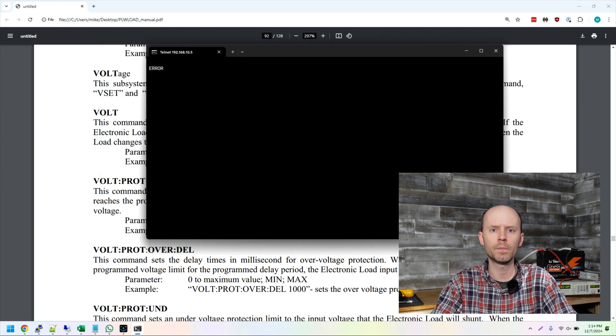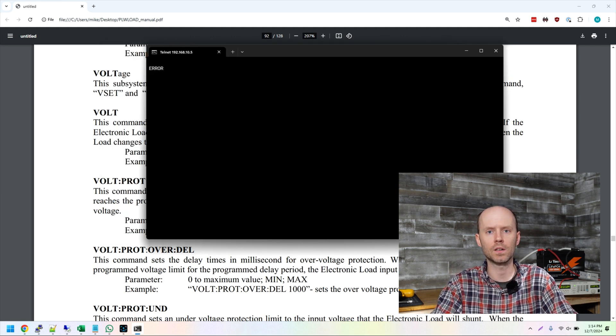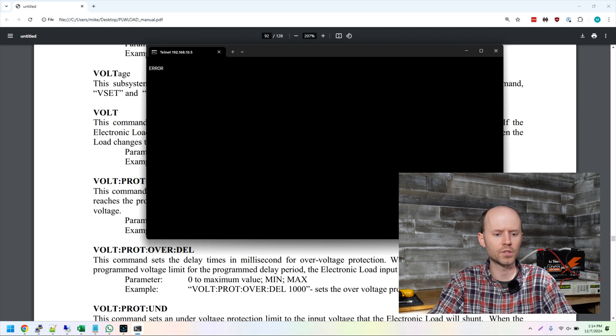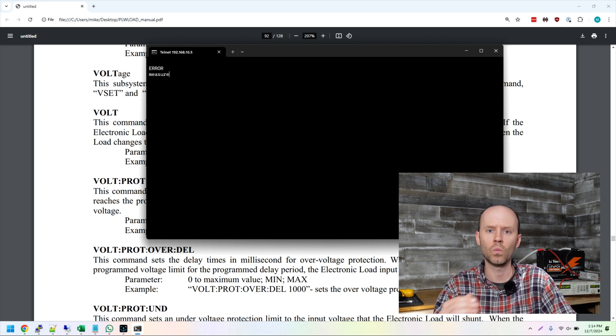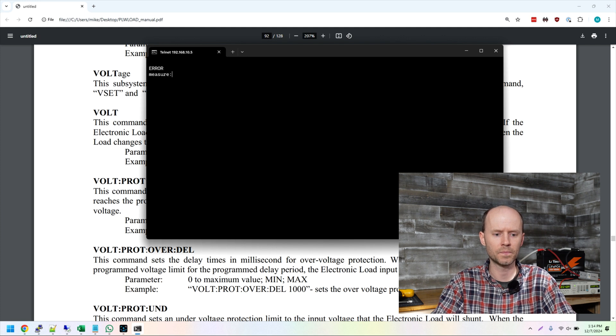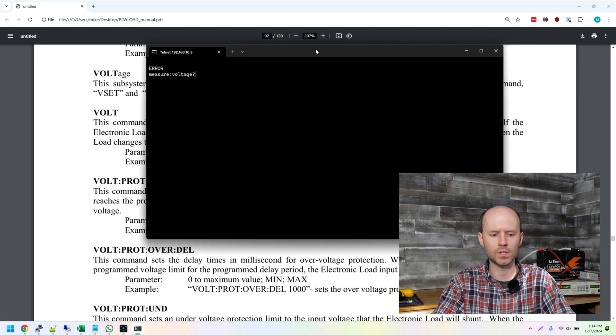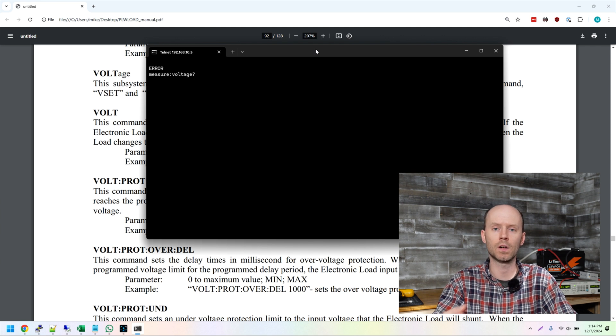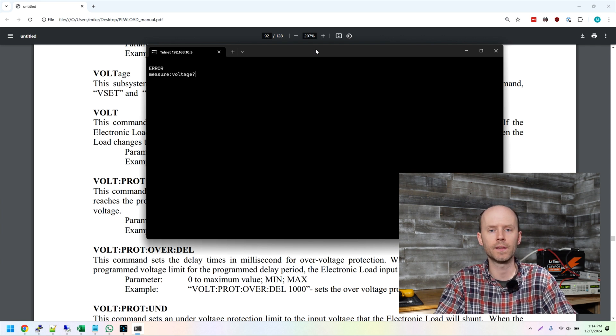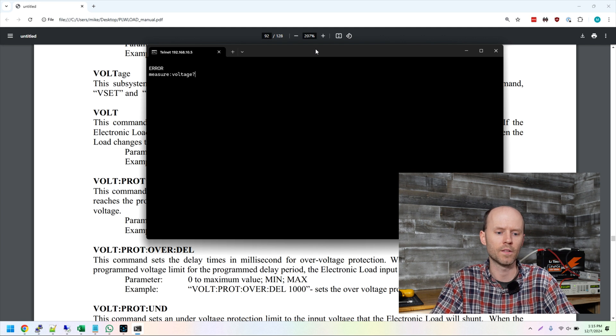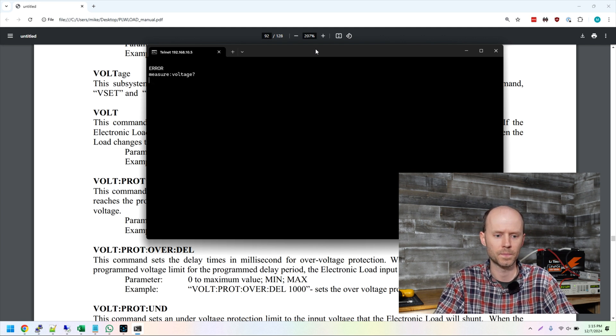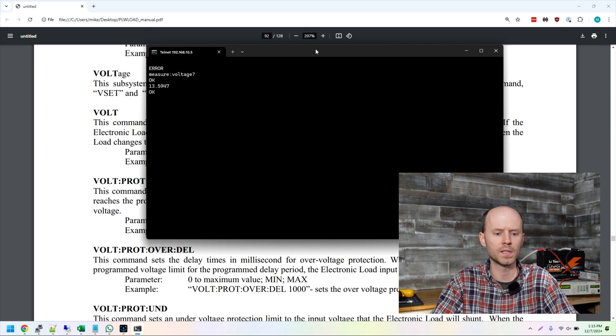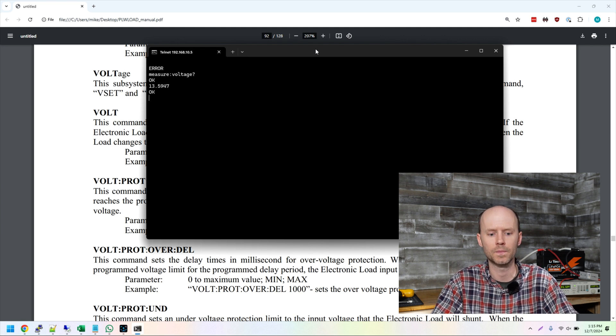So the two primary bits of information I need to calculate and run a capacity test are the current voltage and the current current. So to do that, we're going to use the measure command. And it's a multiple part command. We need to tell it what we are measuring. So we're going to put a colon and I want to measure voltage. And then I'm going to put a question mark. So whenever you run a command that you're expecting a result to come back that you're querying, you put a question mark to indicate that that statement is a query. So we have measure colon voltage question mark. Press enter. And you can see it responds with OK. And it sends back 13.5947 volts.